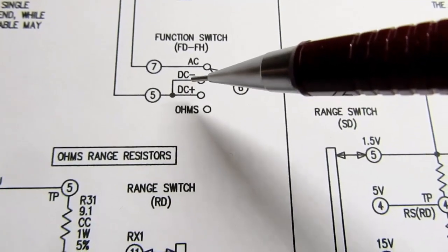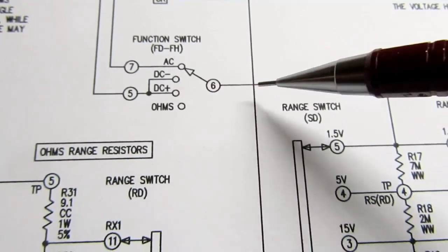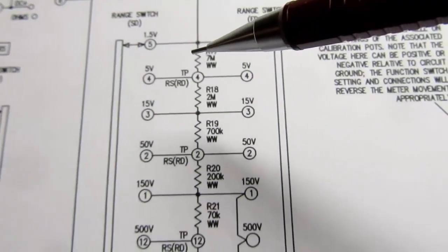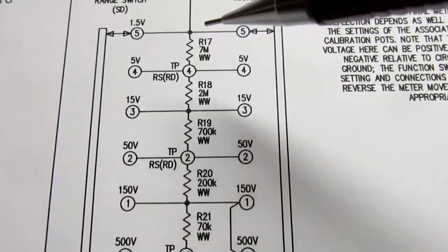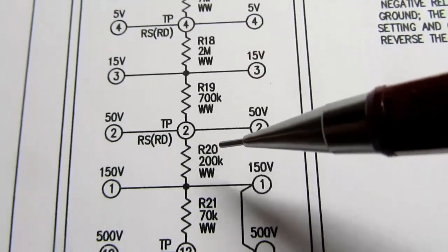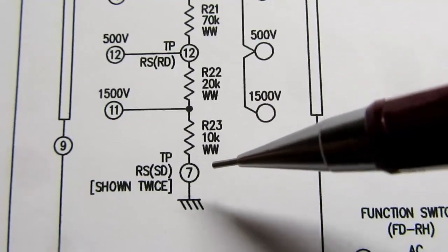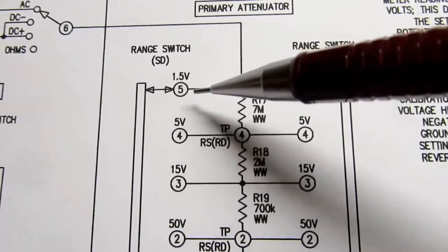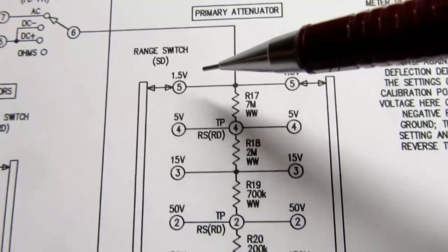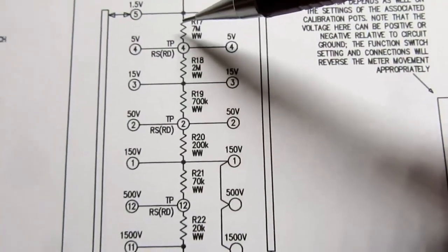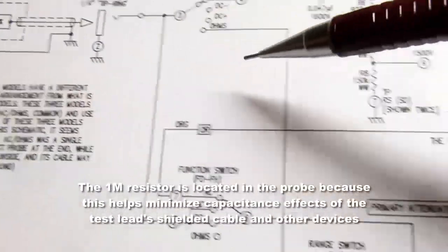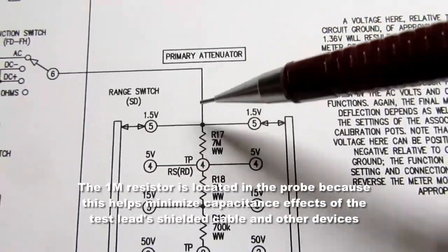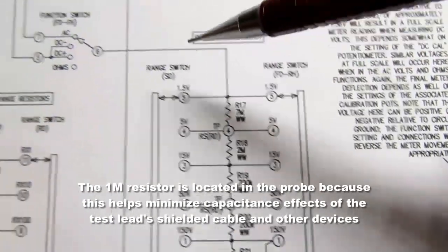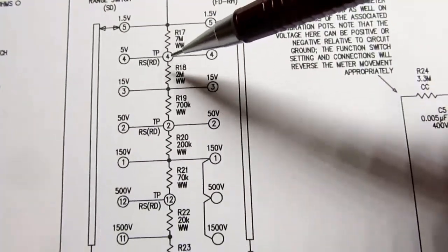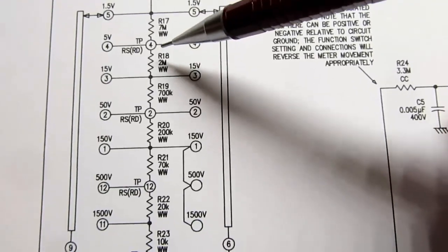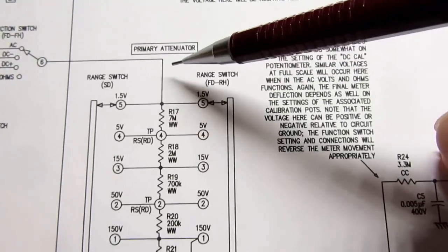And whether you're in DC plus or DC minus position on the function switch, that signal just passes through and is presented to the top of the main or primary attenuator circuit. This has resistors 7 megs, 2 megs, 700K, 200K, 70K, 20K, and 10K, finally ending up at circuit ground. So if you were in the 1.5 volt range, for example, you would have all these resistors added up in series, and then the 1 meg resistor here as the top resistor in this voltage divider. Think of it as being right here. So almost all the voltage being measured from the probe will be dropped across the much greater resistance here. All of these, by the way, add up to 10 megohms. And then you've got that 1 megohm sitting on top.